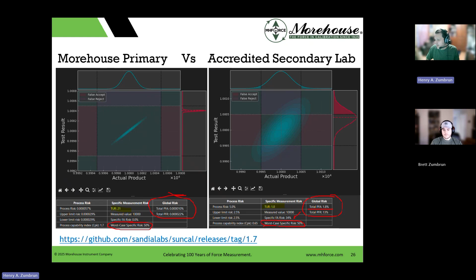So I'm applying some type of guard band, and the specific false accept risk is 34%. That's what we had last time. Process risk, other things - basically that's saying okay, I can kind of control my risk here, and I'm going to call it the penalty here because I have such large uncertainty, back to the PFR. It's saying on a global scale, I'm getting 13% of the population where I'm going to make that wrong decision - I'm going to say it's actually bad when they're actually good.